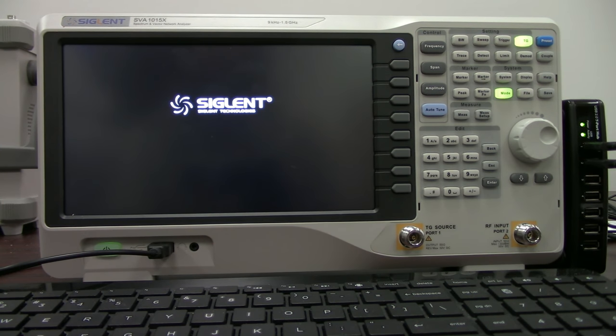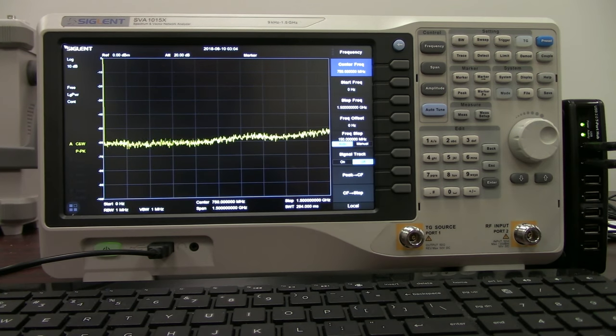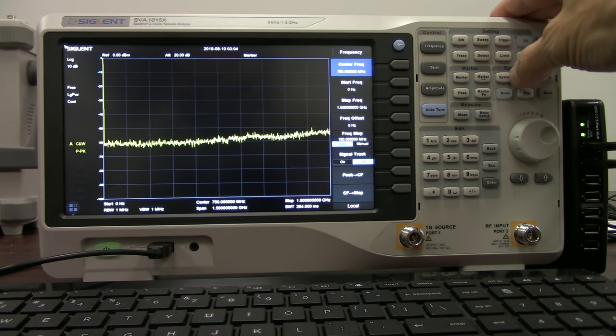The power on line is going to be extremely helpful if you have the instrument in a remote situation. Maybe on the top of a mountain or in a building that you don't have access to. The instrument will automatically turn back on if we enable power on line.